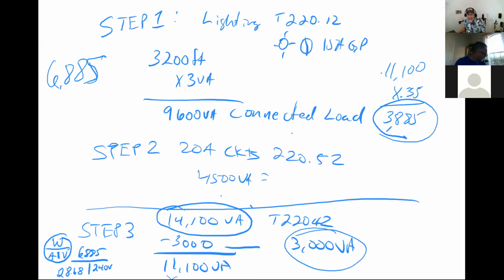If they were to ask me for a branch calculation for the same house, same everything, my branch calculation would be 14,100 because I wouldn't be allowed to use the feeder table for the derating, since that's under a different part. They could ask me for a connected load or a branch circuit calculation, and it would be 14,100 because we'd be calculating under part 2, but we wouldn't derate it unless we're doing feeders in part 3.